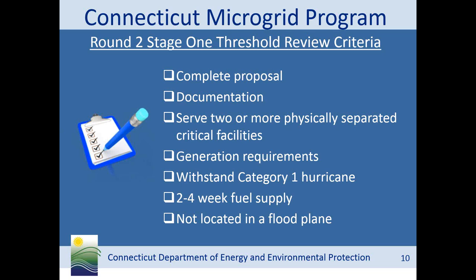The new generation in the microgrid was capped at 25% diesel, had to operate for a minimum of 7,000 hours annually, which basically made it 24/7 grid connected, had to be able to follow the load, had to have excess capacity to withstand any changes in the load, and had to have black start capability.